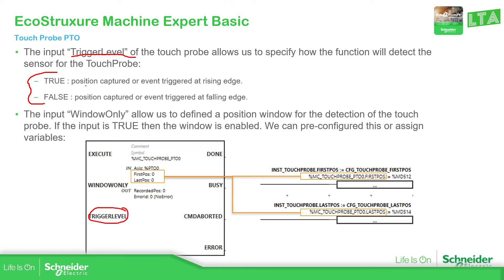True corresponds to the rising edge, and false to the falling edge. Then we have the window only, which requires these two positions for the sensor. This position will be linked to pulse positions. So if you need to have this in degrees or in millimeters or centimeters, you will probably need to make some kind of formula to define this. You can pre-configure these two values, but if you want to configure that in an HMI or something, you will need to link a %MD variable to those. To access that, you will need to select the instance dot the names that you have.